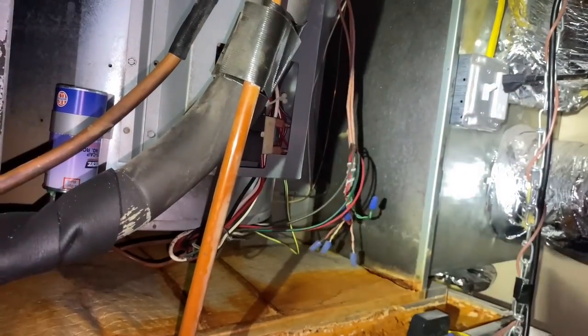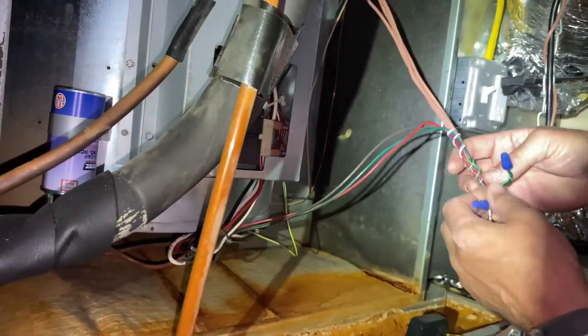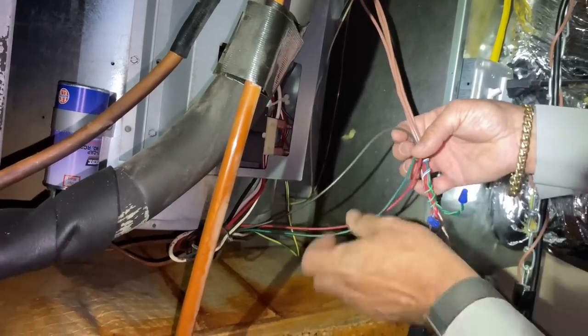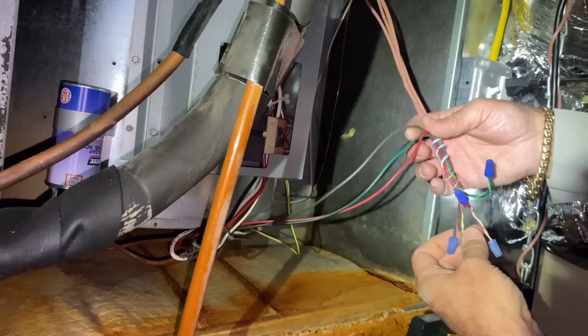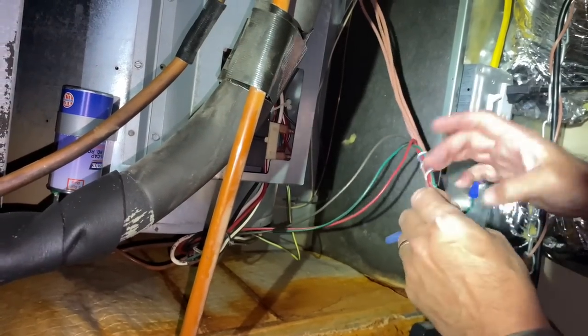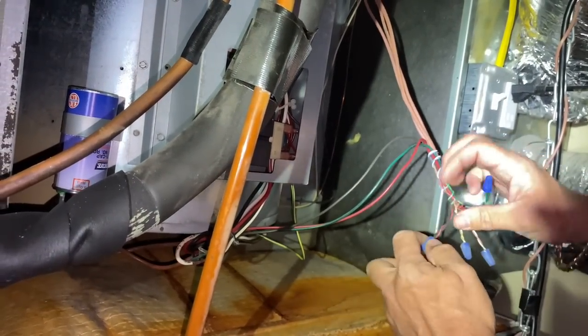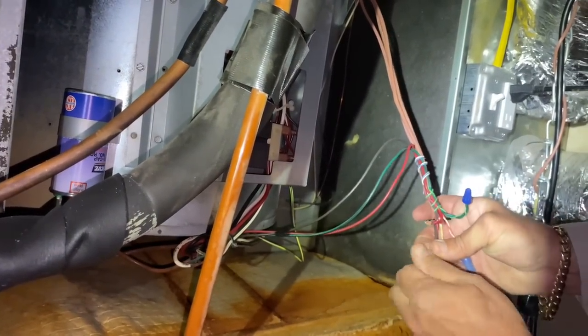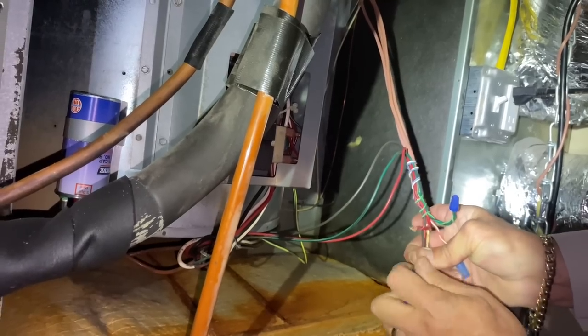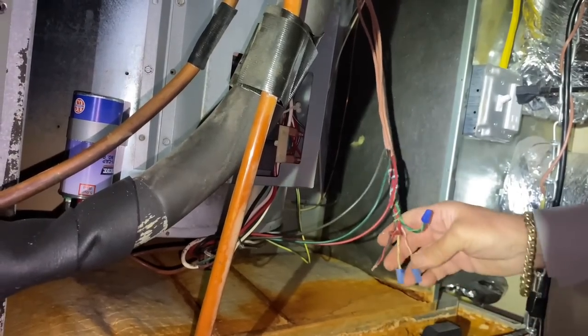We have a hum of the transformer, let's just see. The gray, this black is going to be our common. So let's do our red and common and see if we have 24 volts there. All right, we could have a bad switch somewhere breaking common, but I doubt it.